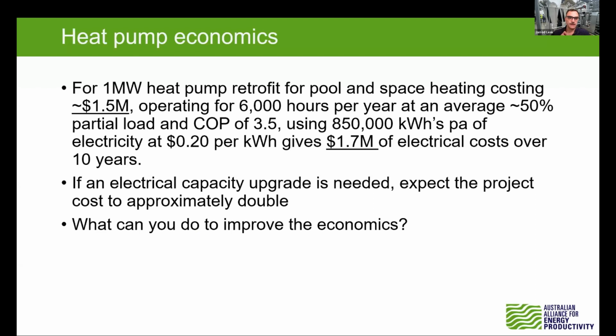So just to give a bit of a framework around what we're talking about today, this is a rough case we want to present. We wanted to show a few scenarios of how you can really move the needle on the economics. If you looked at, say, a 1 megawatt heat pump, that might cost about $1.5 million - I appreciate that's a wide band, but that's not a bad amount to use. Let's say that's operating for 6,000 hours per year at partial load of 50%, with a COP, coefficient of performance, of 3.5.